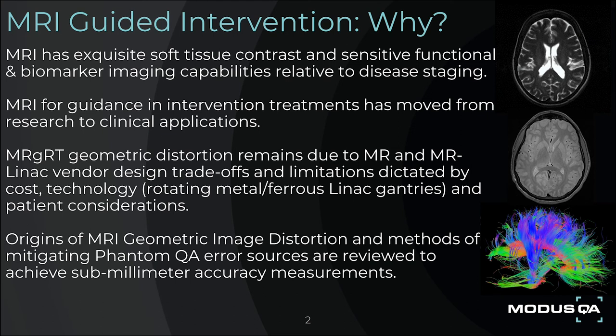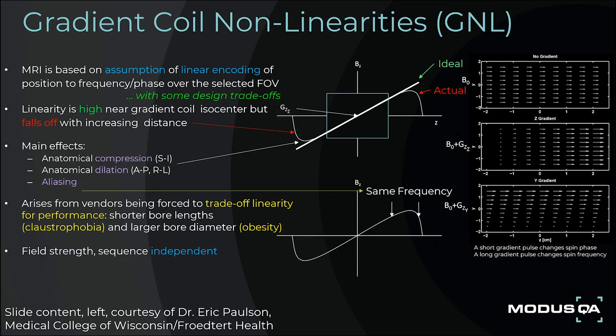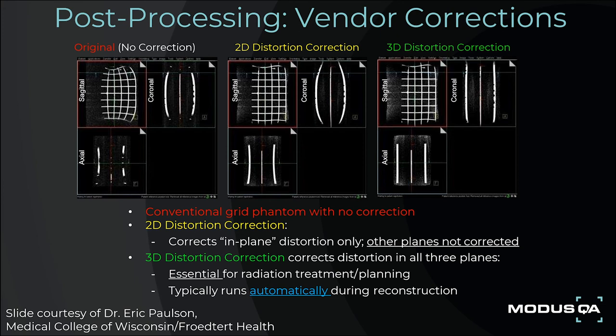Origins of MRI geometric image distortion and methods of mitigating phantom QA error sources are reviewed to achieve sub-millimeter accuracy measurements. All MR manufacturers design gradient coils with some design tradeoffs and limitations dictated by cost and patient considerations. It is not practical to design MR systems sufficiently long with small enough bores to ensure gradient coils are optimized without software correction, as this would lead to excessively heavy, costly, and impractical systems. Practical design considerations and required tradeoffs will lead to gradient nonlinearity with increased distance from ISO center. All MRI vendors employ software correction of gradient coil nonlinearity in 2D and 3D imaging, applying the correction based on harmonic analysis of the uncorrected fields to produce distortion-corrected images suitable for diagnostic and guided treatment applications.